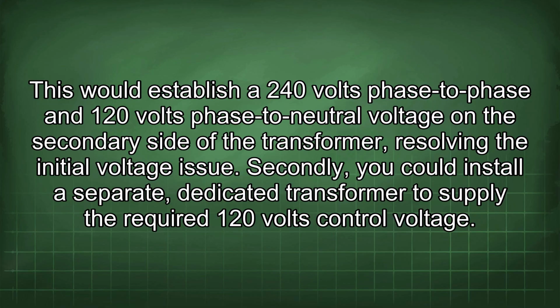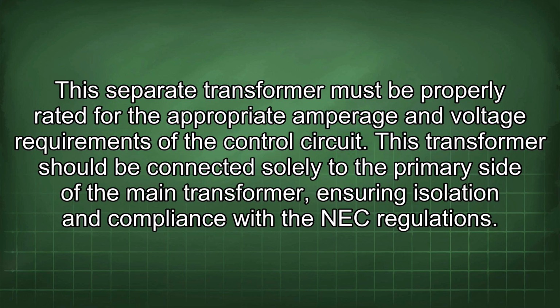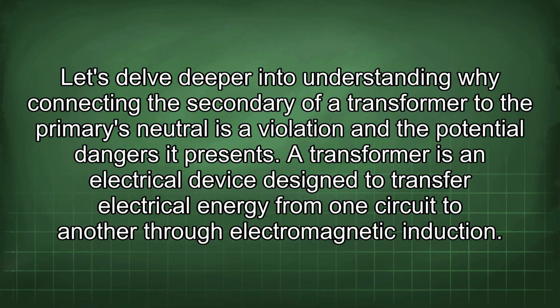Secondly, you could install a separate, dedicated transformer to supply the required 120 volts control voltage. This separate transformer must be properly rated for the appropriate amperage and voltage requirements of the control circuit. This transformer should be connected solely to the primary side of the main transformer, ensuring isolation and compliance with the NEC regulations. Let's delve deeper into understanding why connecting the secondary of a transformer to the primary's neutral is a violation and the potential dangers it presents.